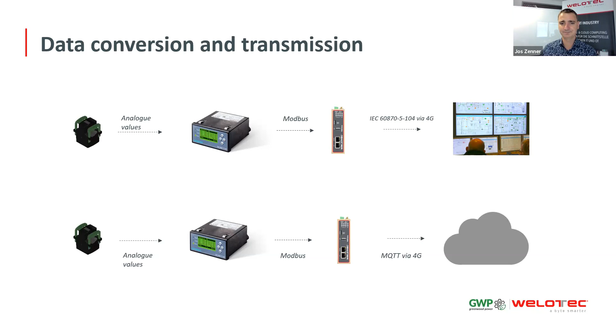The full setup looks even more complex, but it's still quite easy. So we have the different types of sensors, which are low power current transformers, low power voltage transformers, but also low voltage current sensors that are connected to multiple FCMs within the secondary substation. So you usually find between 3 and 10 FCMs in one secondary substation. And they all can be connected over Modbus RTU and the RS-485 bus to one gateway. So one gateway, in this case the TK600 from Welotec, can take the data, convert the serial data into Ethernet data, and transmit it over a secure connection to the SCADA or cloud system.